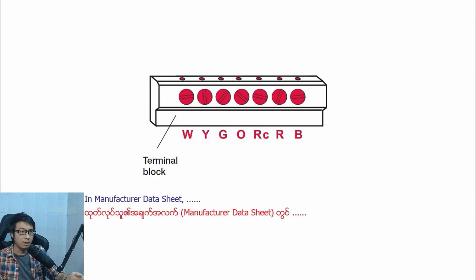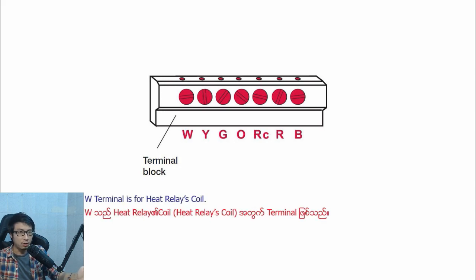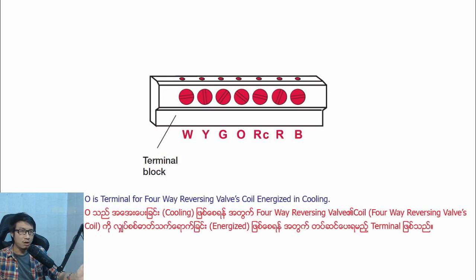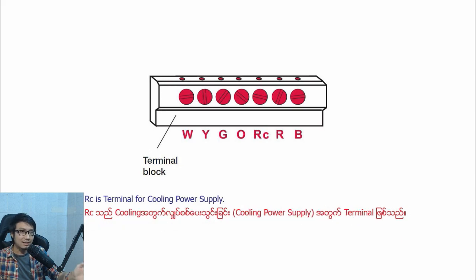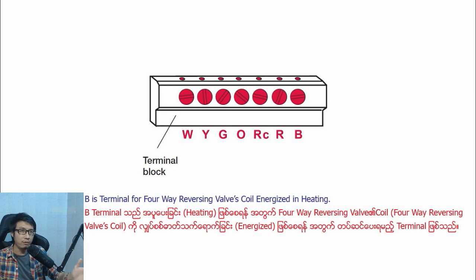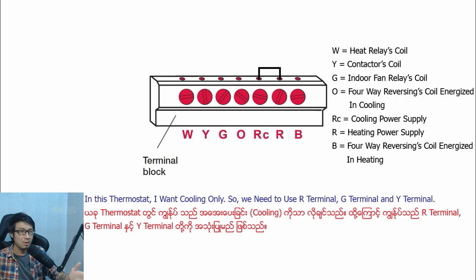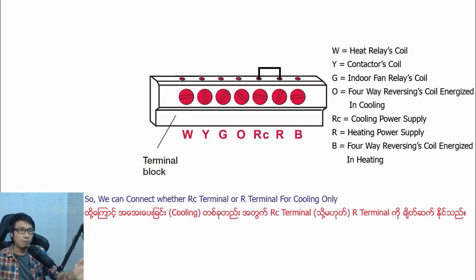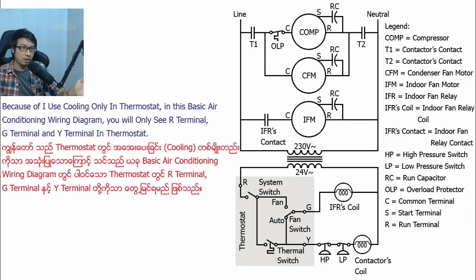In the sub-base of the 24V AC thermostat, wires need to connect to the terminal block. According to the manufacturer datasheet: the W thermostat wire is for the heat relay coil, Y thermostat is for the contactor coil, G thermostat is for the indoor fan relay coil, O is the thermostat for the four-way reversing valve coil energizing cooling, RC is thermostat for cooling power supply, R is thermostat for heating power supply, and B is thermostat for the four-way reversing valve coil energizing heating. In this thermostat, for cooling only, we need to use R, G, and Y thermostat wires, and jump a wire from RC to R thermostat.